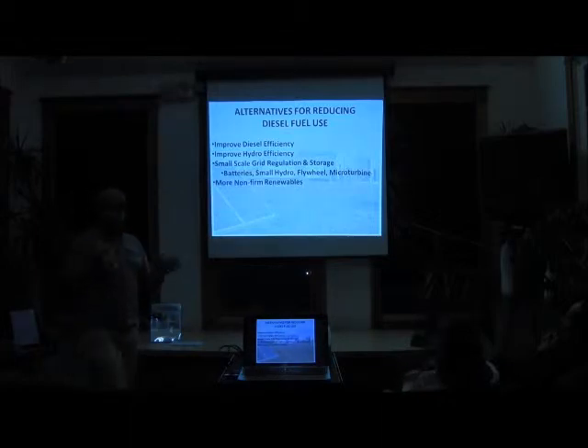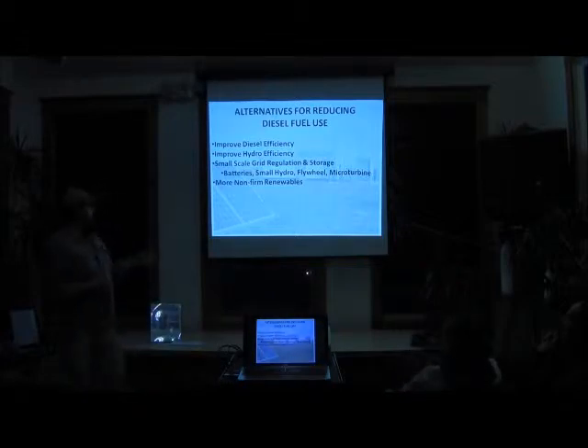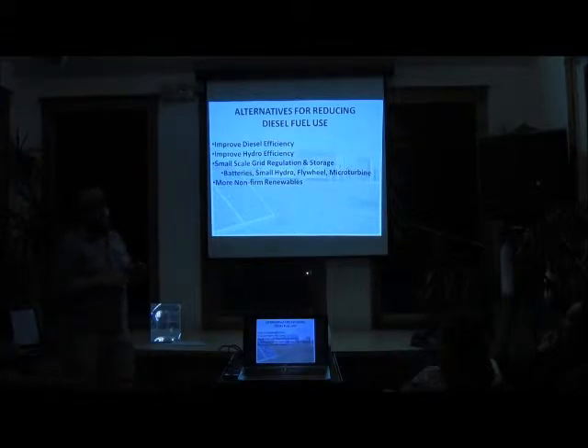And when I say firm, a diesel generator is firm, hydro is firm, because as the load changes, we can follow it. So if everyone turns on their toaster oven, we can put more fuel in the diesel generator and it produces more electricity, or open the nozzles on the hydro. Non-firm is wind, solar to a certain extent, tidal power. You can't control it, so the wind could be blowing and all of a sudden everyone turns a bunch of stuff on, but the wind could stop blowing and you can't make it blow any harder.